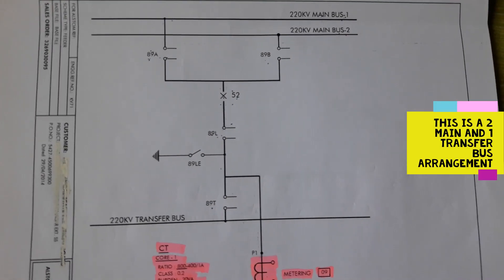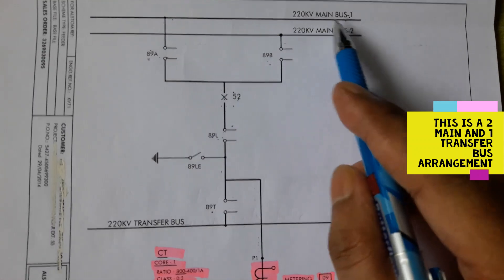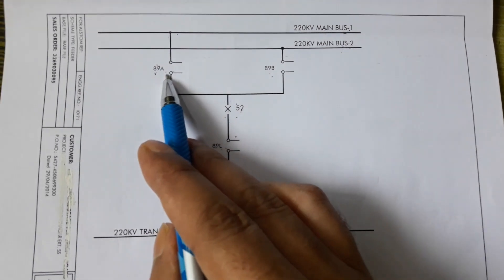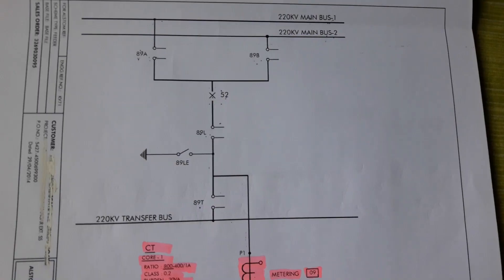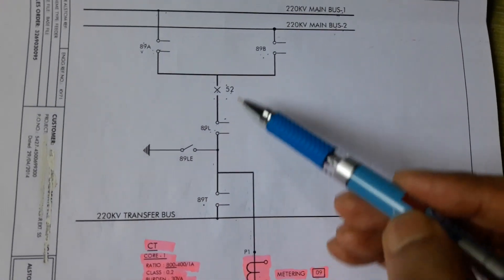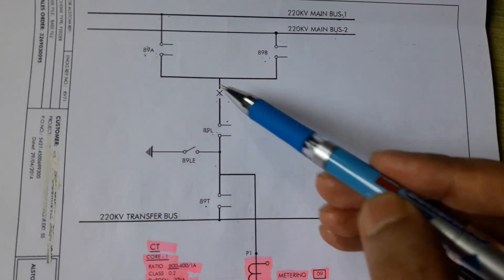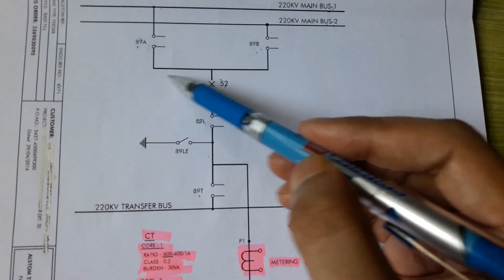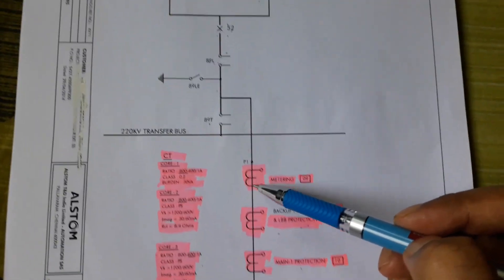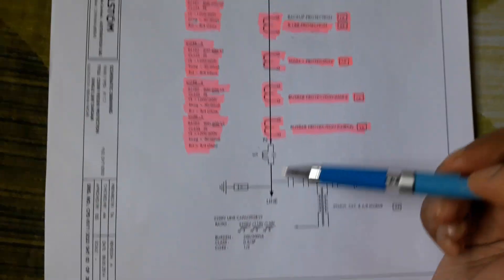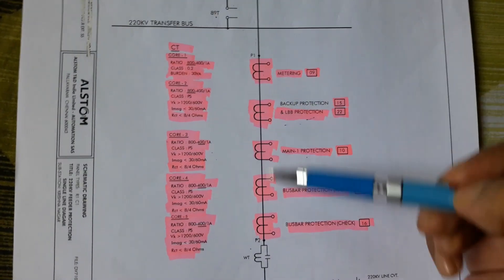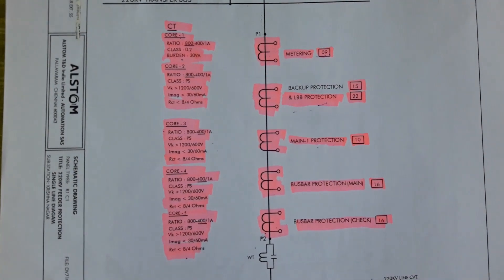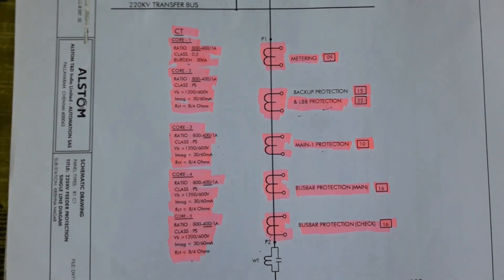This is the 220 kV feeder bay which may be connected with main bus 1 or main bus 2 by connecting either 89A isolator or 89B isolator. Suppose 89A, 89L and 52 breaker all are closed, then this bay is connected with main bus 1 and the load will flow through this CT. P1 and P2 represent the primary start of the CT, which has 5 number of CT secondary cores.